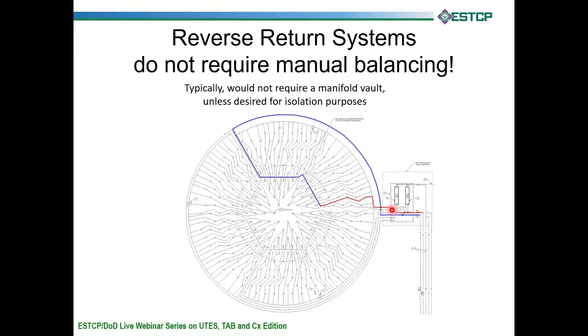So our water's coming in here on the red, and it hits this first circuit here. We're going to call these sub-circuits. And this area right here is called a trisector in our design. We had 3 trisectors, and each trisector had several sub-circuits. So this is just one trisector here, and we hit the first trisector first. Our supply comes in, hits the first trisector. Well, when it hits the return main, it is the last sub-main to hit the return main. So it's the first one to leave, but it's the last one to be picked up by the return.